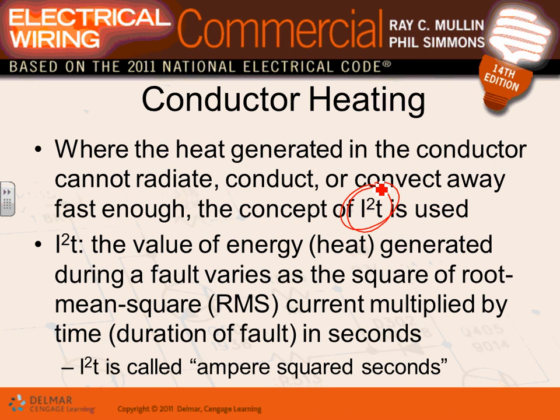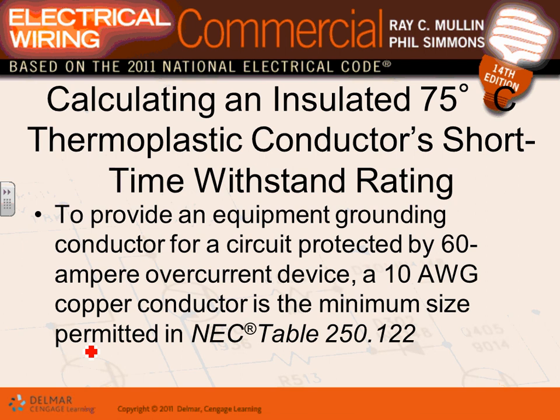The heat generated in the conductor has to be radiated or convected away. That's what typically happens in normal operating conditions: the circuit will heat up and the heat will dissipate, radiate, convect away from the conductors. In a short circuit condition, there's not enough time for the heat generated by the short circuit to dissipate. So what's going to happen? It's going to sit there and cook the equipment. So welcome to the I squared T. That's the term we use.